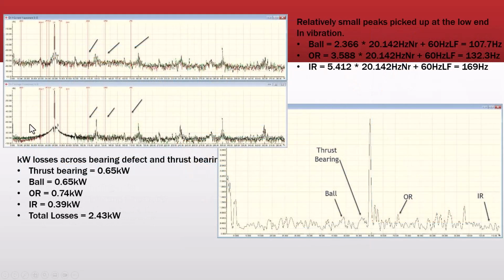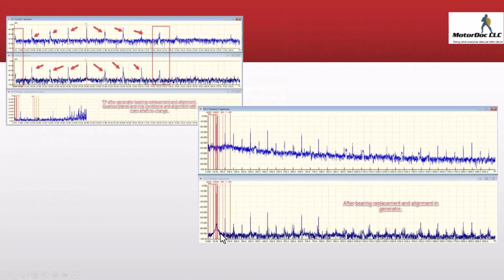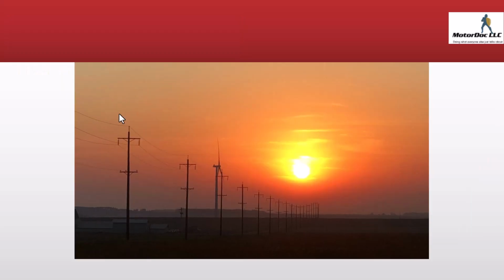Now, changing it out, we didn't eliminate all the losses. We just reduced them all the way down because we've reduced the friction, but there's still friction losses. There always has to be. So to suggest that it would be zero would be a bad idea. So about 2.5 kilowatts remained. Everything was dealt with, but the big thing with this generator, when everything was said and done, they weren't going to be back up there replacing everything a short while later. So with that, the time test worked out perfectly, and you guys will get to enjoy the benefit of this.